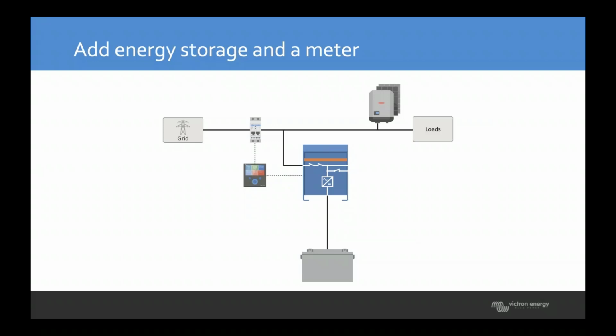One of the ways we do this is with an energy meter in a system like this. So you can see that in the diagram, connected to our GX device. And this energy meter will look to see if there's any import or export of power. So if the system is importing power, the battery will discharge through our Multi-Plus. And if there's export of power, then it will charge the battery.